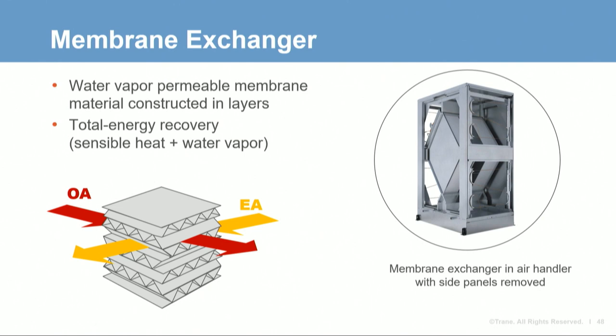A variation of the fixed plate heat exchanger is the membrane exchanger. Instead of aluminum plates, a vapor-permeable membrane can be used to exchange both sensible heat and water vapor. Like aluminum plates, the airflows are cross-flow and sensible heat is exchanged. However, in addition to heat transfer, water vapor is transferred between airstreams through the membrane via permeation — water vapor permeates to the airstream of lower water vapor pressure.